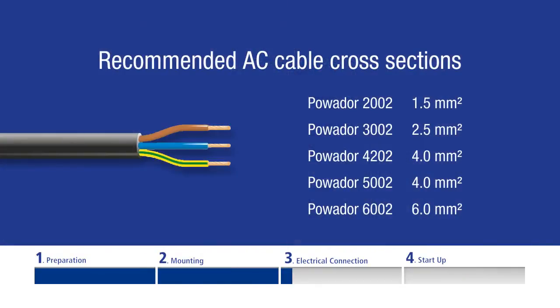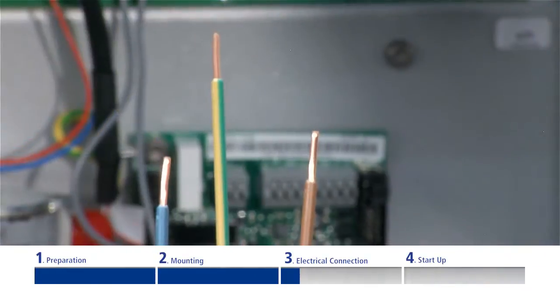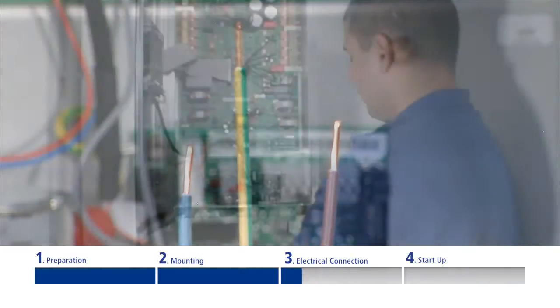Be sure to use cables with a sufficiently large cross section. This prevents excessive line impedance between the mains distribution board and the inverter. Excessive line impedance will lead to the inverter being switched off due to grid over voltage.